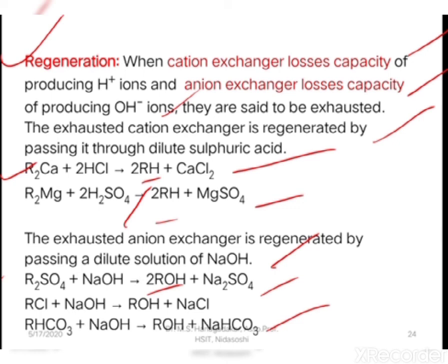As a result, once the performance of the ion exchange process becomes poor, regeneration is performed by cleaning the cation exchange resin with sulfuric acid or hydrochloric acid, and the anion exchange resin by passing dilute NaOH, in the respective compartments.